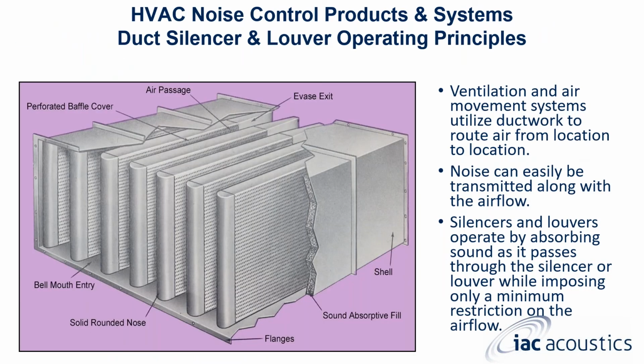Duct silencer and louver operating principles. We'll start off here with the duct silencer. So as you can see, it has the bell mouth entry. We have the evase exit, the air passage, perforated baffle cover, flanges, sound absorptive fill, the shell, you name it. This is a very good picture of what an interior silencer looks like.